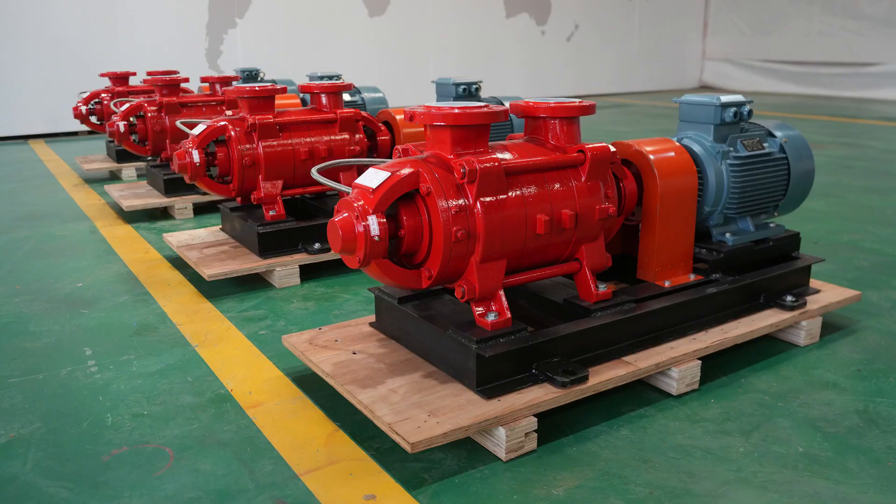The article also hit some common questions. Basic function: sends water to the boiler to make steam, keeps the boiler topped up like keeping your water bottle full on a hike. Four main types: horizontal multistage, vertical multistage, stamped stainless steel vertical inline, and heavy-duty horizontal ring section — each for different pressure and space needs. For sizing, match boiler pressure and flow needs; pump pressure must be higher than boiler pressure, and check NPSH. Common failure reasons: cavitation, dirty or corrosive water, wrong size pump, and skipping maintenance. General maintenance guideline: checks every three to six months, always following the manufacturer's specific guide.